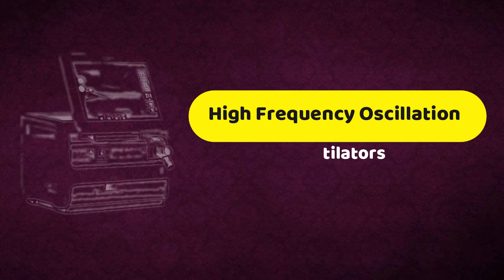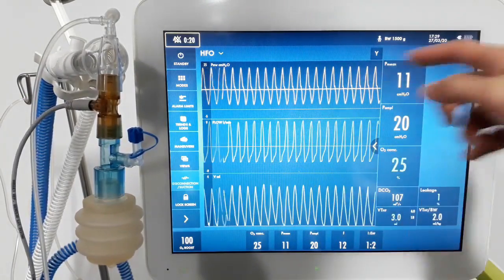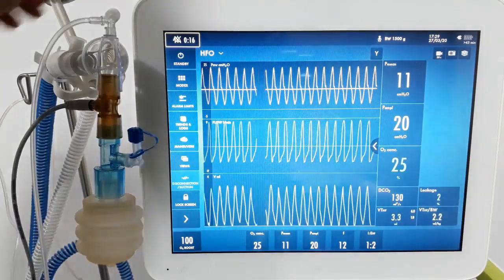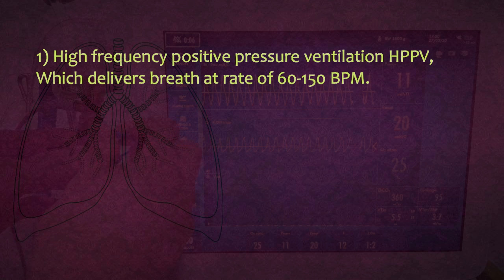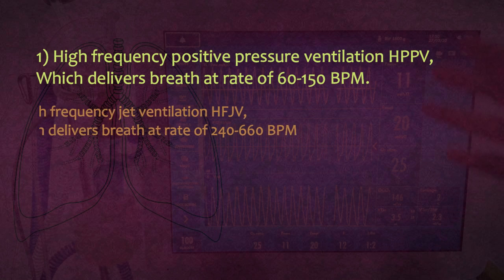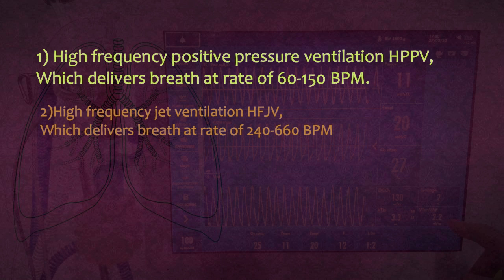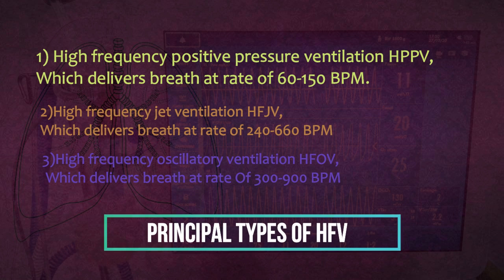The next classification is the high-frequency oscillation ventilator. HFV is a new technique of ventilation that uses respiratory rates greatly exceeding normal breathing. There are three principal types of HFV: (1) High Frequency Positive Pressure Ventilation (HPPV), which delivers breaths at 60 to 150 BPM; (2) High Frequency Jet Ventilation (HFJV), which delivers breaths at 240 to 660 BPM; and (3) High Frequency Oscillatory Ventilation (HFOV), which delivers breaths at 300 to 900 BPM.